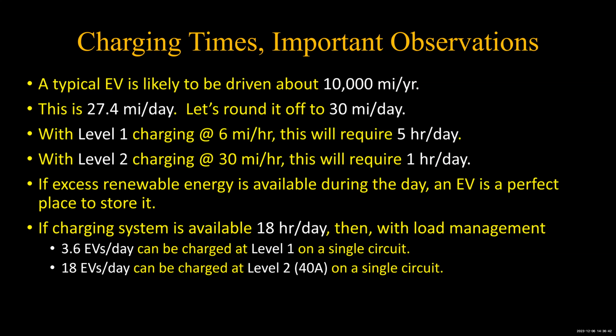Well, then you can do 3.6 EVs a day at level 1, or you can do 18 a day at level 2. 18 on a single 50 amp. I see it says 40 amps here, but that's 40 amps of charging current. It needs a 50 amp breaker. So on a single 50 amp circuit, you can do 18 cars a day. A lot of people don't think about that.